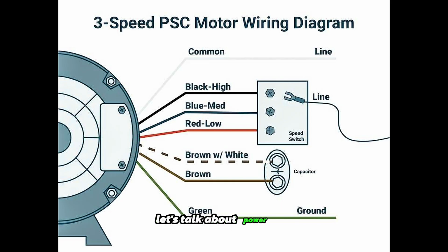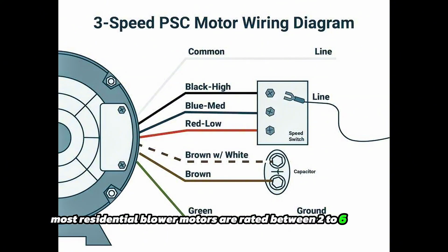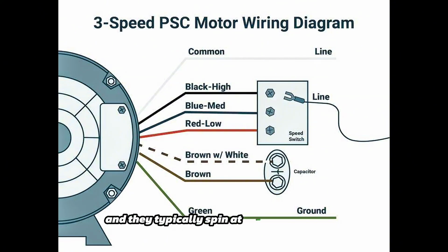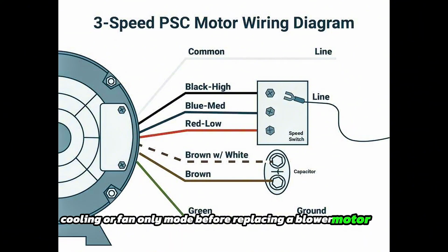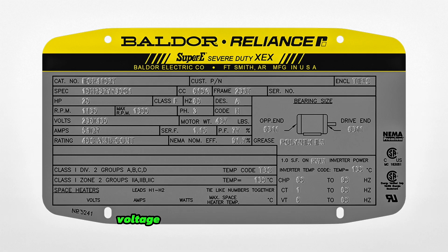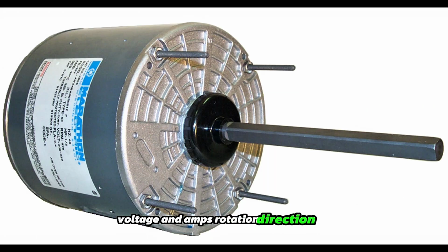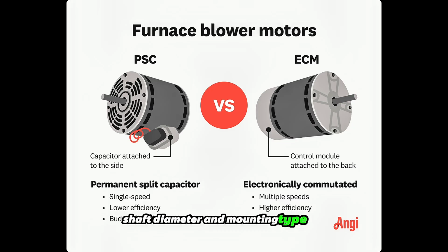Let's talk about power. Most residential blower motors are rated between 2 to 6 amps, and they typically spin at 1050 to 1200 RPM, depending on whether it's heating, cooling, or fan-only mode. Before replacing a blower motor, always check the nameplate voltage and amps, rotation direction, shaft diameter and mounting type, and whether it's PSC or ECM X13.